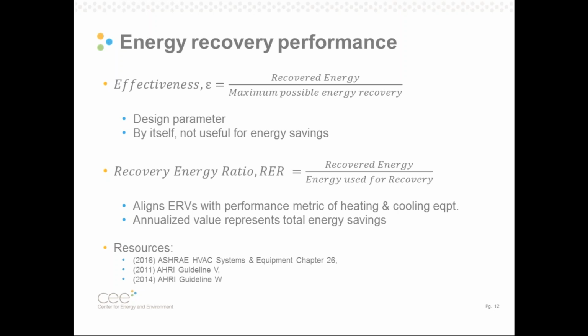We often consider ERVs as passive components, and that's mostly true. Wheels, however, take a small amount of energy in the form of a motor that has to spin them. But all energy recovery units, even ones without moving parts, use energy because they put another pressure drop in our airstream, and we have to use fan power to overcome that pressure drop. So there's an energy cost there. And the RER then tells us how much energy we're recovering versus how much we're using.